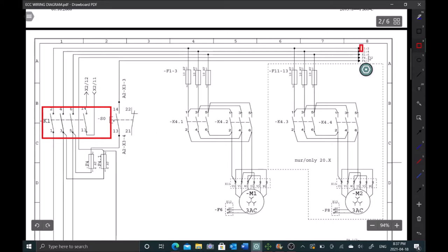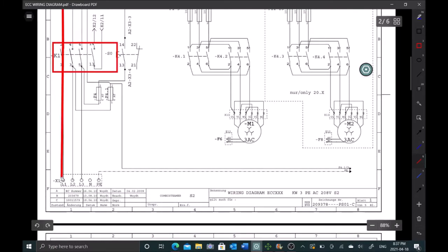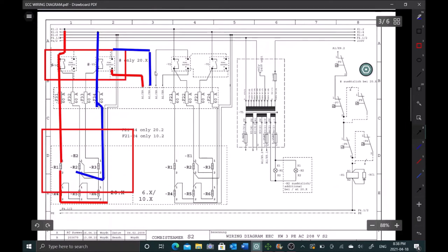You can see here K12, K14. Let's trace this guy back, and if this goes back to our L1, then we know we're on the right path here. If we follow this, you can see through here we're right at our L1. So we've just drawn the complete circuit. Actually, the first time this guy blew, it actually blew this contactor as well. So the issue could be here, it could be in these relays, or it could be in these elements. I'm leaning toward it's going to be in one of these elements just because the intermittent shorting, the spacing between, it's so far apart, every three weeks. Let's go there and let's go examine these elements a little bit further.